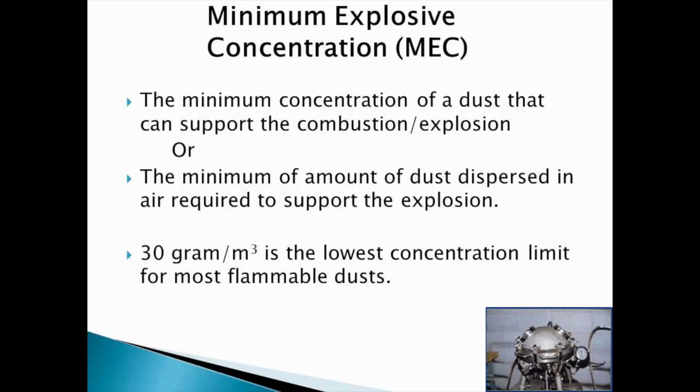Minimum explosive concentration, or MEC. It refers to the minimum concentration of combustible dust and air required to propagate the flame. MEC is dependent on the size of the particle, the temperature of the ignition source, and the amount of oxygen in the air. A combustible dust cloud cannot be ignited when its concentration is lower than MEC.